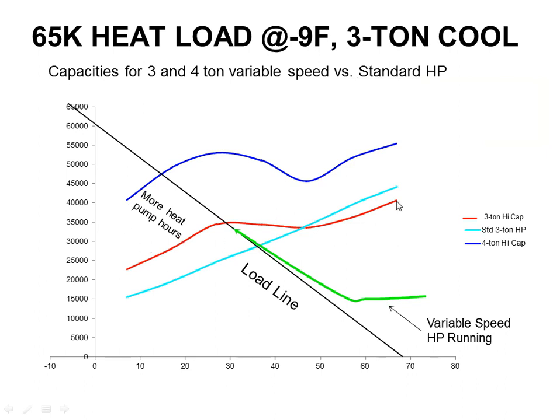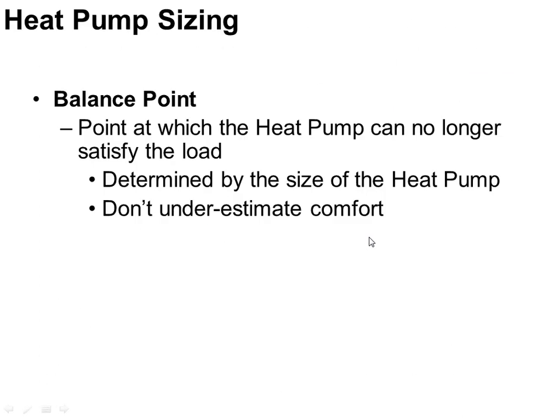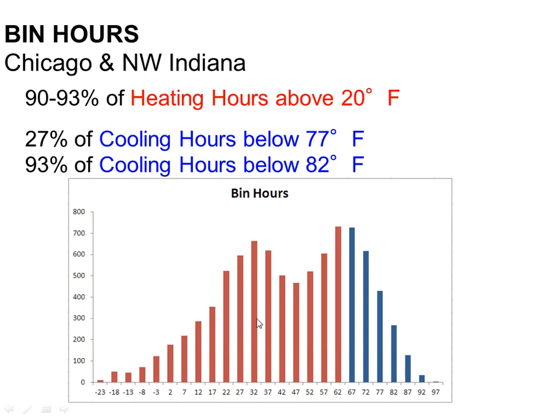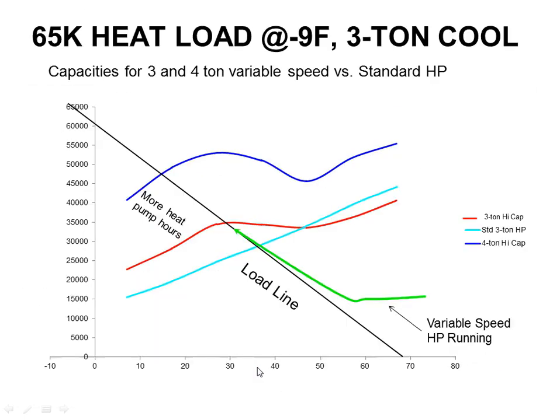If I put in the 3 ton variable speed heat pump, it then becomes this red line here. So that red line, as you can see, is a little bit flatter, not quite as steep as the baby blue line, because I'm able to control the compressor and condenser fan speeds in order to continue to maintain the BTUs that I want. So now I can get down to about 30 degrees outside air temperature, which is a bit of an improvement. And if you look back a couple charts, between 30 and 35, we're talking about an extra 600-700 run hours that I might be able to get if I did that, just by going to the 3 ton variable speed.